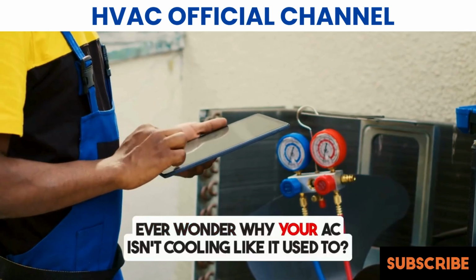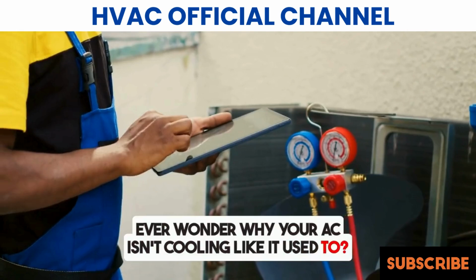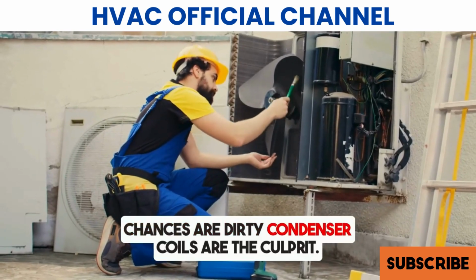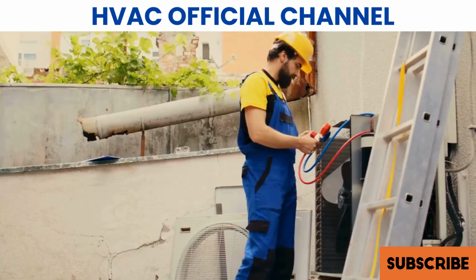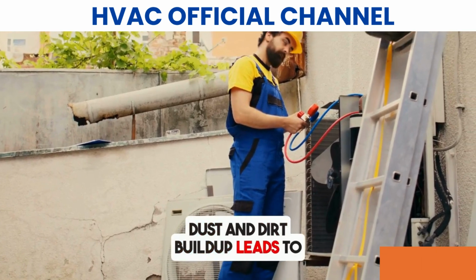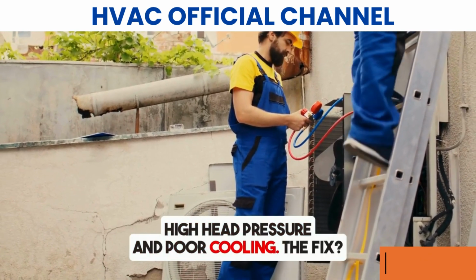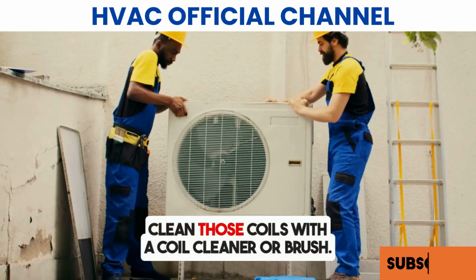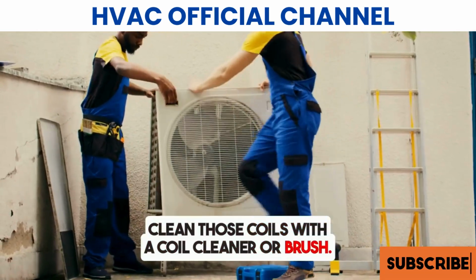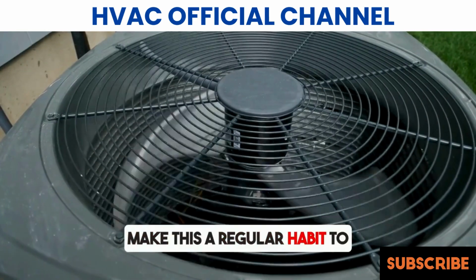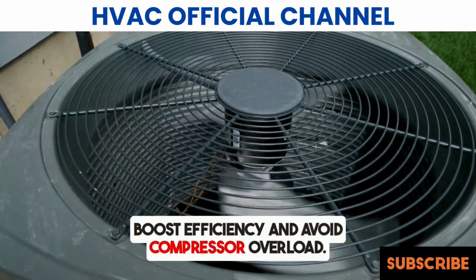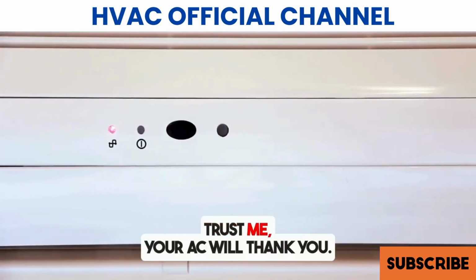Ever wonder why your AC isn't cooling like it used to? Chances are, dirty condenser coils are the culprit. Dust and dirt buildup leads to high head pressure and poor cooling. The fix? Clean those coils with a coil cleaner or brush. Make this a regular habit to boost efficiency and avoid compressor overload. Trust me, your AC will thank you.